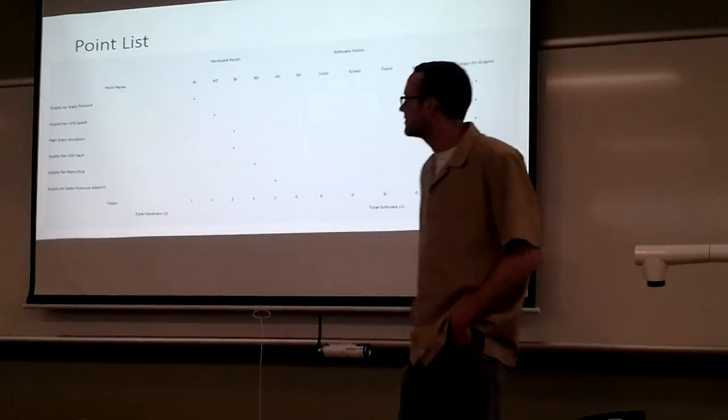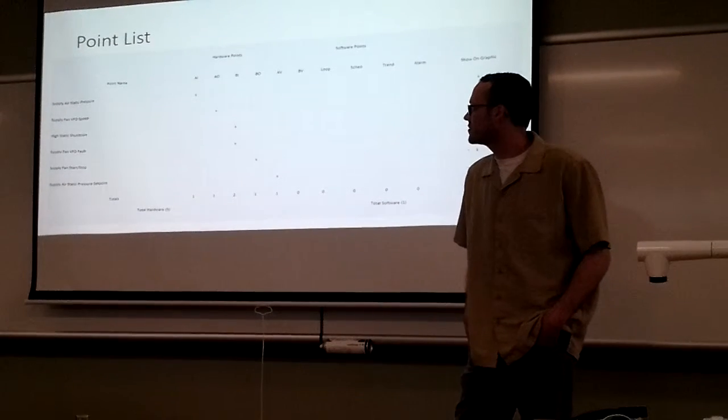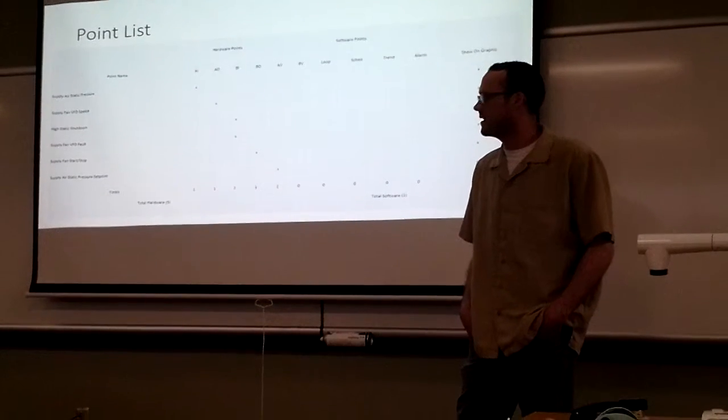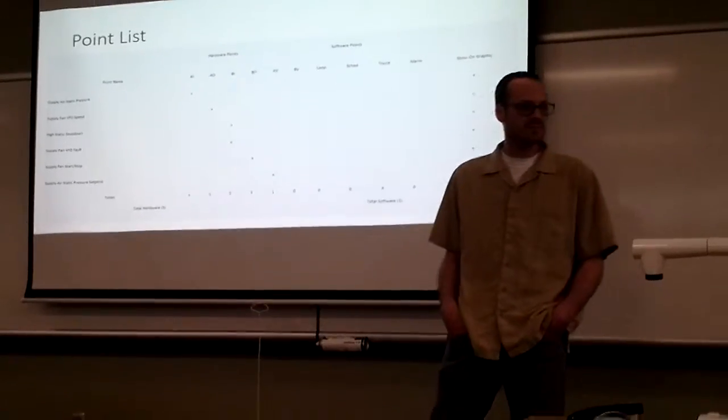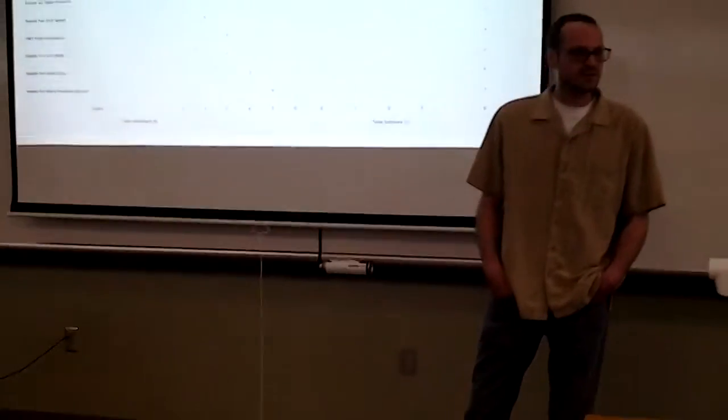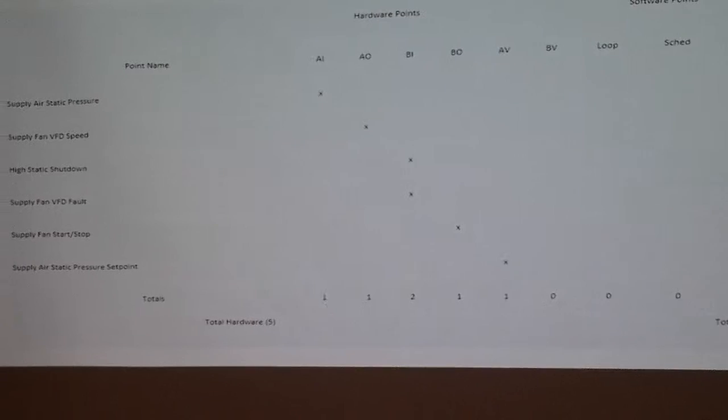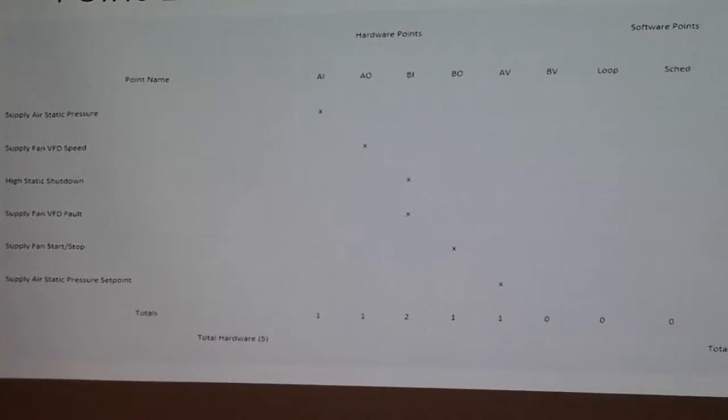Our points list, we have static air pressure and that's an analog input. We have a supply fan speed VFD, that's our analog output. We have a high static shutdown which is a binary input. We have a supply fan VFD fault and that's another binary input.